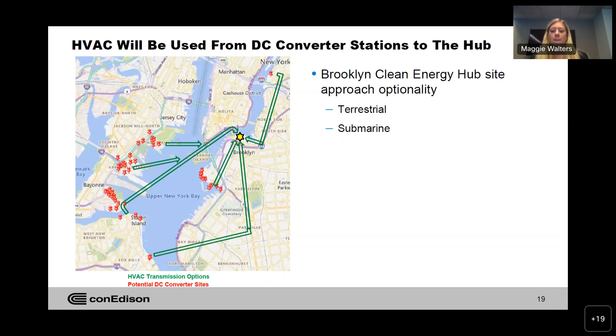We received questions about the technical challenges of routing both high voltage DC and AC cables in the same waterways. We've spoken to cable manufacturers and large consulting firms about this. When designing transmission cables that cross existing power cables, there are multiple means and methods to protect each cable, depending on installation characteristics, including a protective sleeve at each crossing for minimum separation, or a concrete mattress laid between cables for protection. These methods are included in the approved project plan for the Champlain-Hudson Power Express project, which involves installing high voltage DC cables through the Harlem River, crossing existing Con Edison high voltage AC cables.